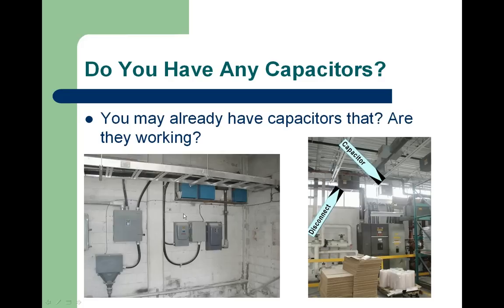You can see the cursor, we have 3, I think these are about 50 or 60 kVAR fixed capacitors mounted up on a wall above some disconnect switches. And over on the right side here, we have a site that has a disconnect switch actually up in the ceiling space. I'm losing my mouse here, sorry. And we have a capacitor bank mounted high up. And these are cases where, as plants change with maintenance managers, et cetera, over the years, and even in some commercial sites, people forget that they even have them.